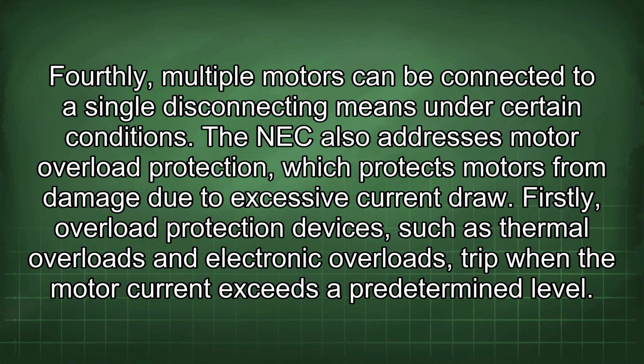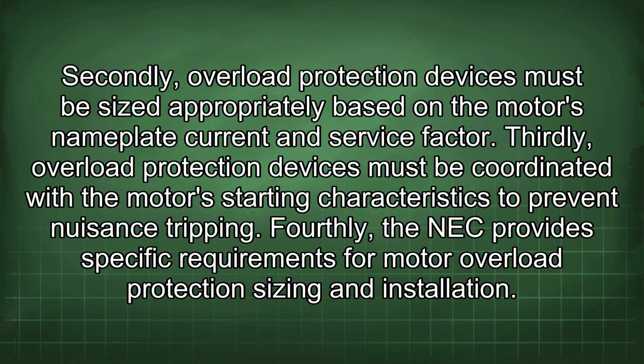Firstly, overload protection devices, such as thermal overloads and electronic overloads, trip when the motor current exceeds a predetermined level. Secondly, overload protection devices must be sized appropriately based on the motor's nameplate current and service factor. Thirdly, overload protection devices must be coordinated with the motor's starting characteristics to prevent nuisance tripping. Fourthly, the NEC provides specific requirements for motor overload protection sizing and installation.